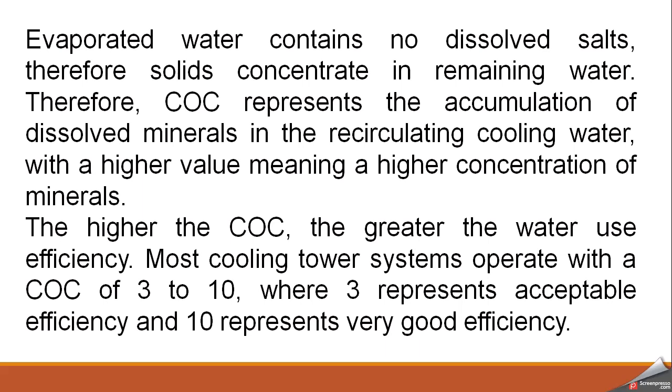if we have a higher COC. If COC is equal to 1, then this becomes a once through system, where water comes in from one side and is then discarded entirely. But if we retain some water, the value goes up and up. For example, if we retain 50% and 50% is discarded, then COC will become 2, and if we discard 1/3 of the water and keep 2/3, then the COC will increase further.